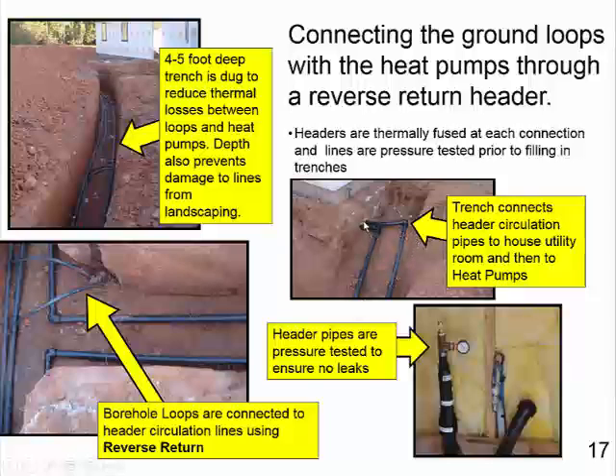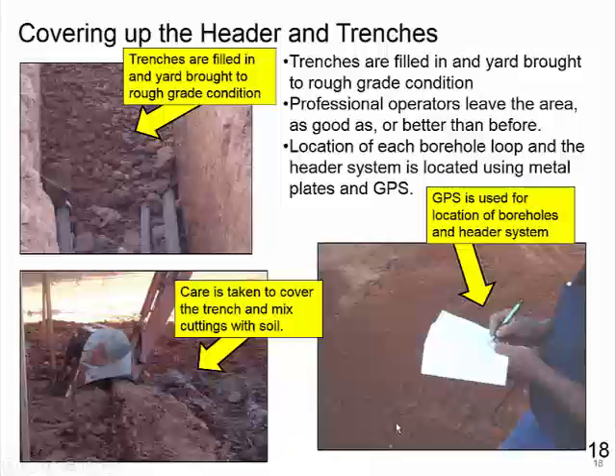Here you see it going into the building, into the utility room in the garage. And the very last stage: the header pipes are pressure tested to ensure no leaks before they're all covered up. This was left on for 24 hours, pressure tested. They came back the next day and it was good, so they started filling the trench in, trying to avoid heavy rocks on the pipes. They mix the cuttings with the soil, and each borehole is located with GPS. I also drew a map of the whole area to show where they're located, and I have that in the utility room.